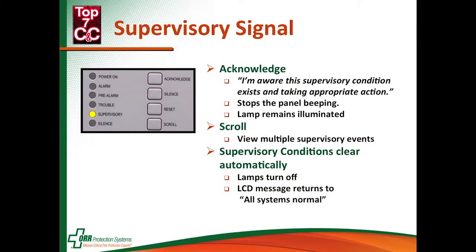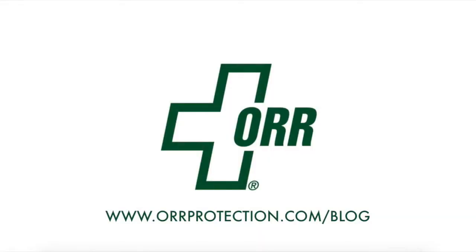The important thing is: supervisory means there's an off-normal condition with another system that the fire alarm system is watching, versus troubles, which are for the fire alarm system itself — that's the distinction. The buttons you can press: acknowledge logs that you acknowledged it, stops the panel from beeping, and resounds in 24 hours. Scroll lets you go through multiple events. And supervisories clear automatically once the offending condition is fixed.